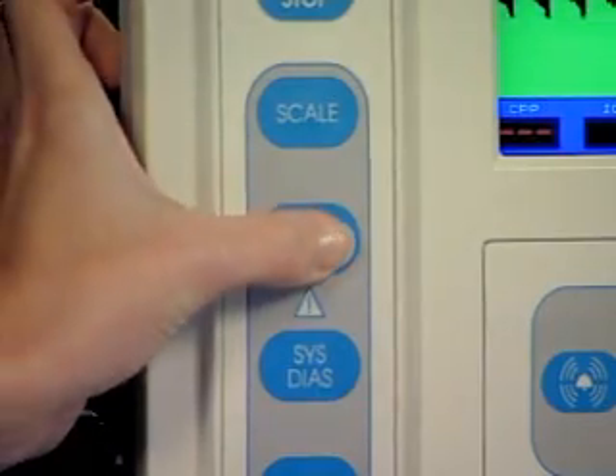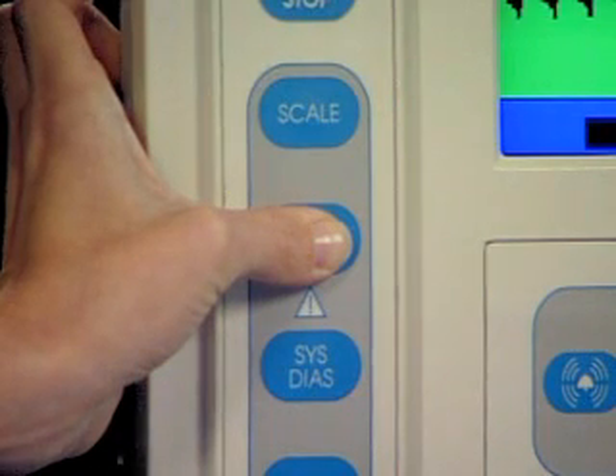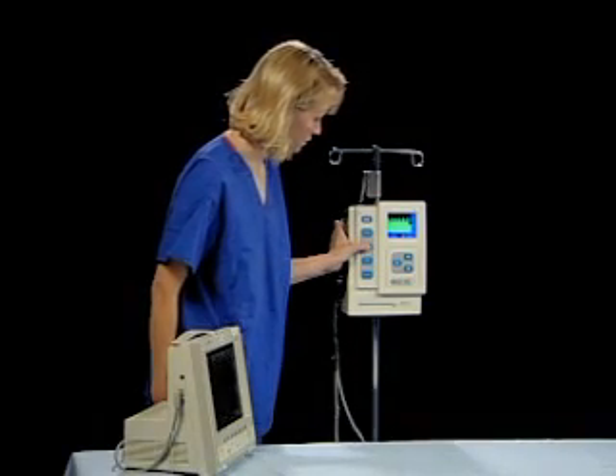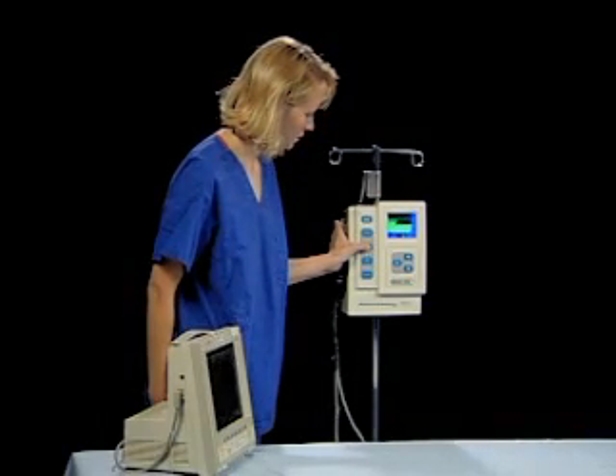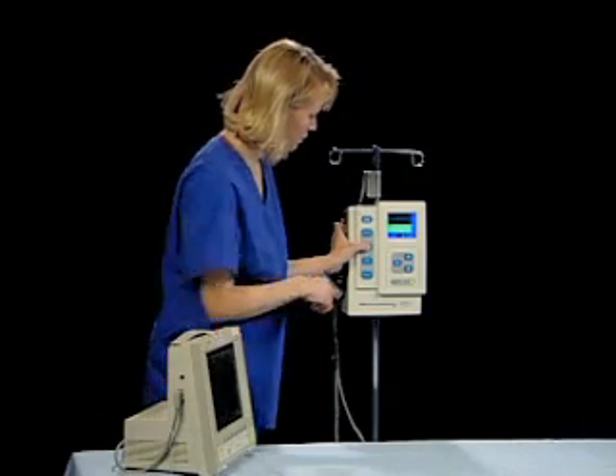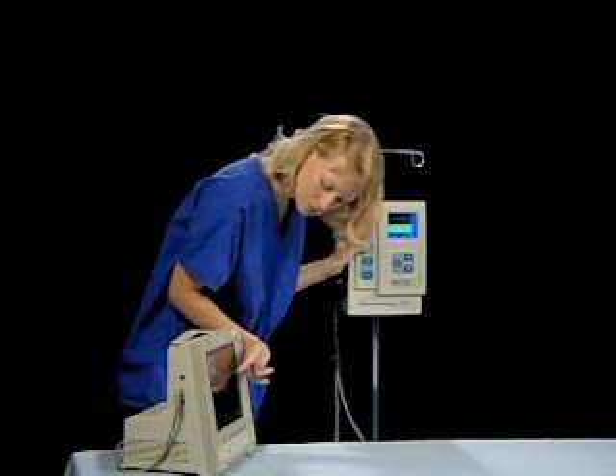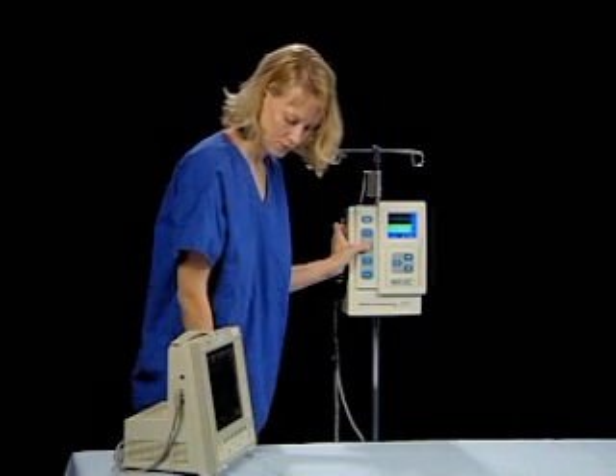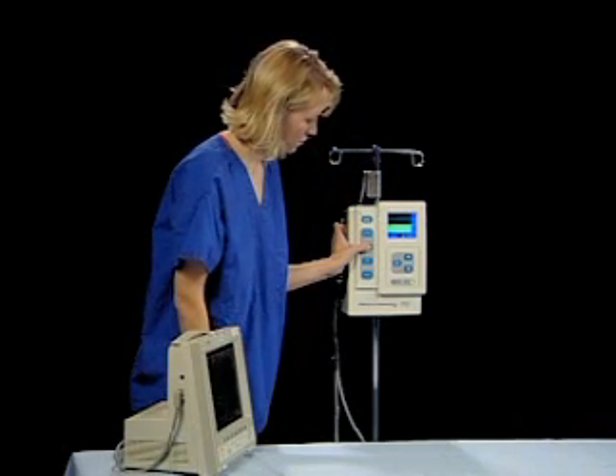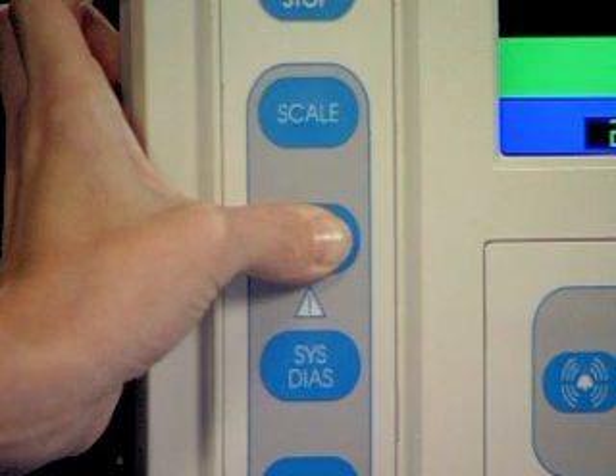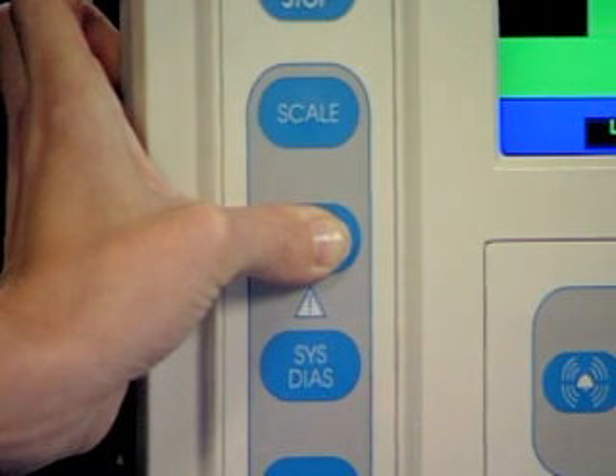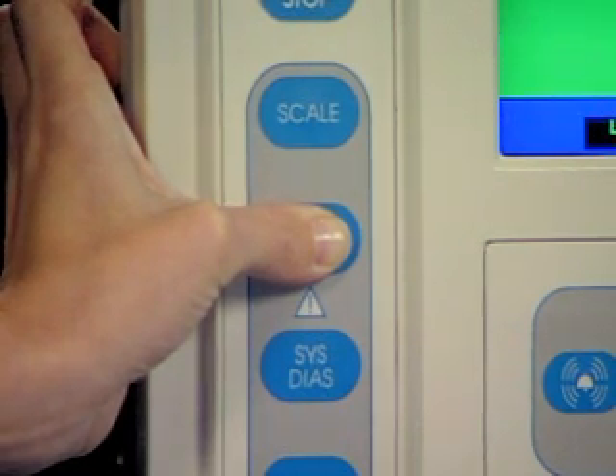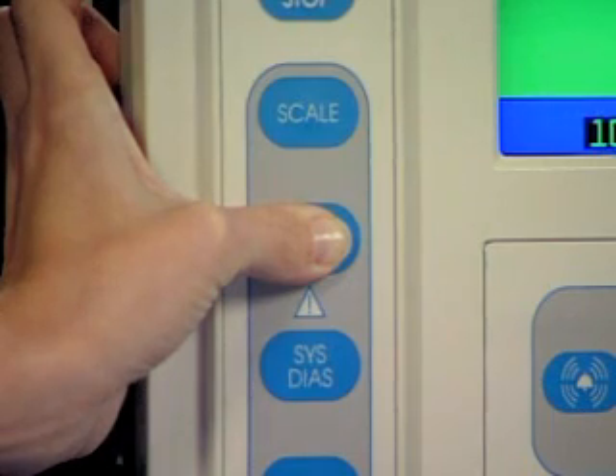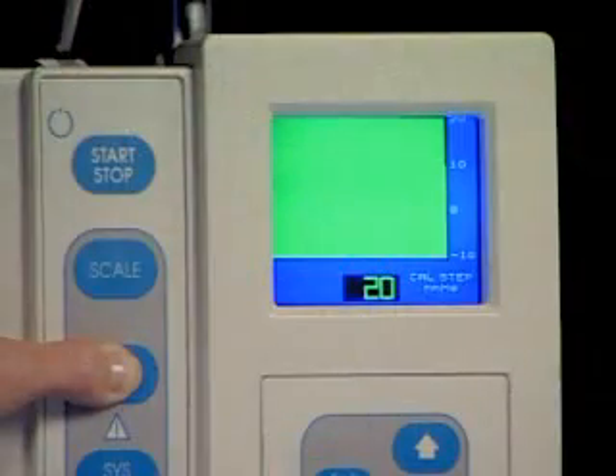The CalStep button is used to calibrate or synchronize the bedside monitor to the MPM-1. Press and hold the CalStep button to initiate a simulated pressure signal that appears on the MPM-1 display screen while simultaneously zeroing the bedside monitor. When both the MPM-1 and bedside monitor display 0, release and press and hold the CalStep button again until 20 is displayed. Confirm that the bedside monitor reads 20.